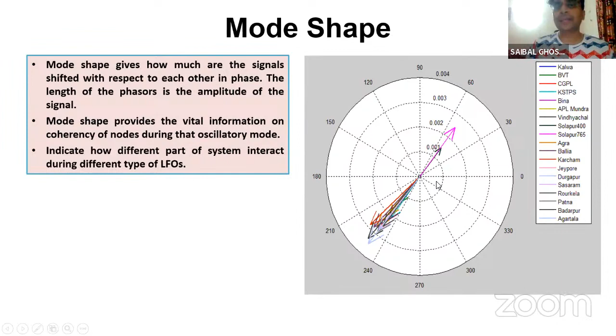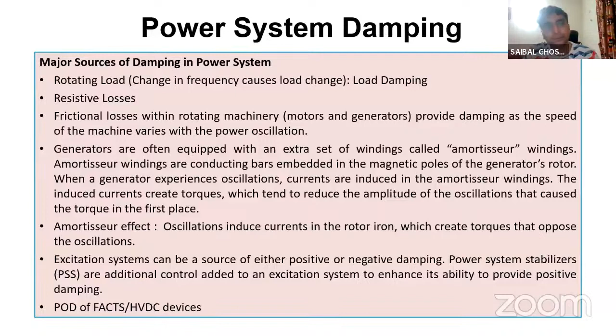A major source of damping in the power system is any resistive load, which is an inherent damping provider in the system. Any rotating load also provides some damping, because they have the same governing equation. Certain extra windings are placed in the generator rotor, the amortisseur windings, and those also provide some damping. Excitation control, the supplementary control called PSS, also provides damping. Other than that, POD is similar to PSS, but it is used with FACTS and HVDC devices to modulate their power flow.